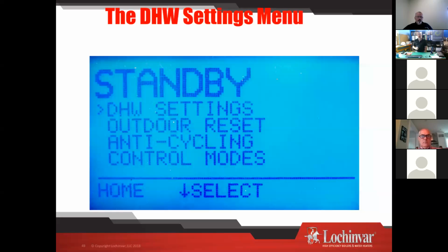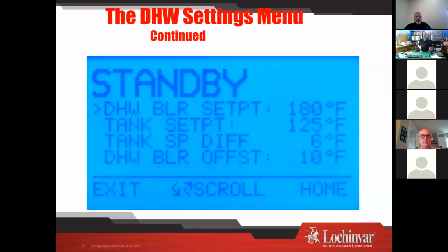Okay, let's talk about some domestic hot water settings. A lot of these only work if you have put the tank sensor in, and that's where the boiler is now reading the temperatures. So boiler set point, and this comes defaulted at 180, and it should almost never be 180. This is the temperature that your boiler is going to run to, firing to heat up its boiler water, is that 180 degrees. That's where this is going to run to. And I'm talking about it in just a second. And it's got a tank set point of 125 degrees. There's always a lot of debate on what my tank set point is, but your boiler set point should probably be about 20 degrees above your tank set point.